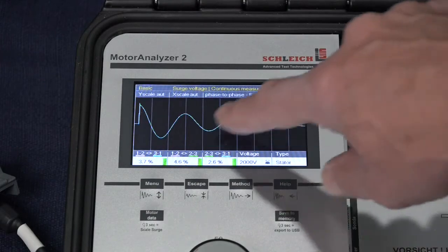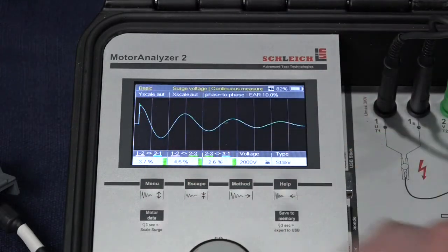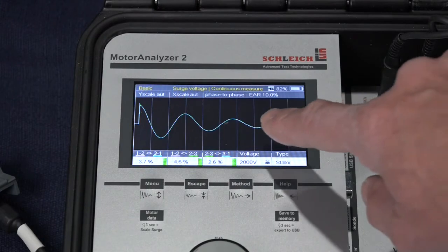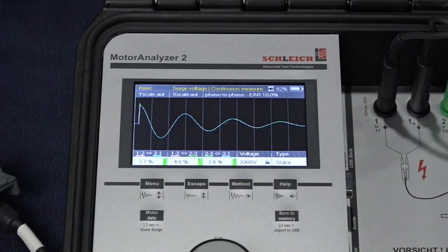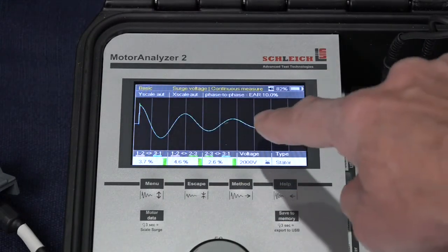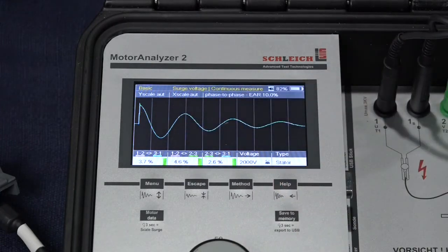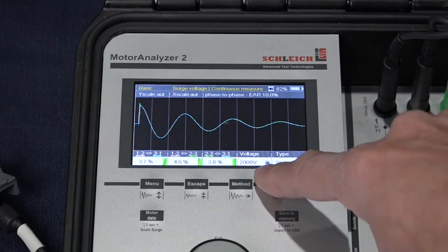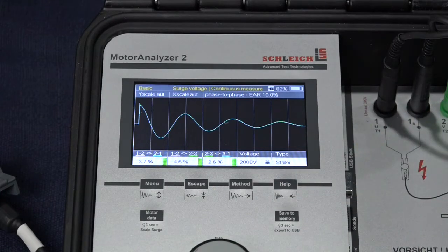As a result, of course, being so similar, they have very low EAR values. Had there been a problem with the stator, like a bolted or welded fault or even an arcing fault, we'd have seen a shift to the left in the waveform. Now, this test was performed very differently than other testers in the industry. We just used 3 pulses at our recommended test voltage of 2,000 volts. We didn't have to ramp up. We got right to where we needed to go and identified the problem. Oh, we didn't find one here. That's very good.